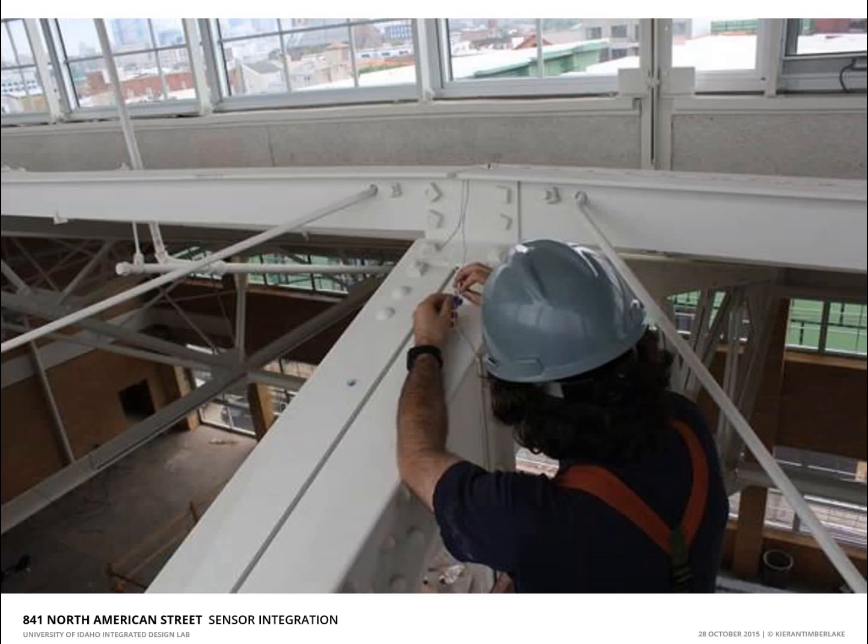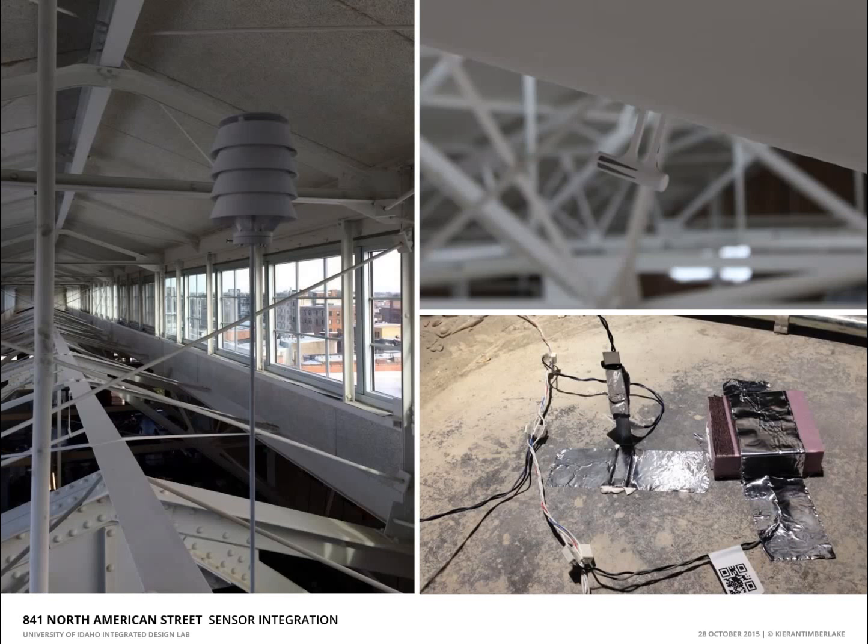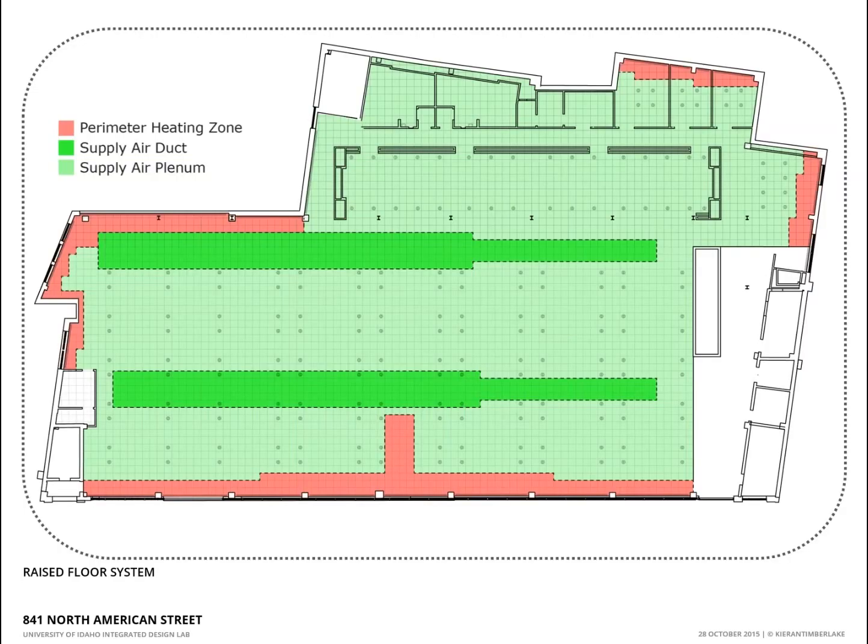So ultimately, we deployed a network that had a very strong performance and aesthetic agenda. So you can see on the left, we have some of these temperature readings taken from the large monitor that we have, where they're shielded from radiation, once again pulling from our own 3D printer to basically print a one-piece radiation shield. Then we also have our relative humidity sensors there on the upper right that we fabricated. And then we have the slab temperature, surface, core, and ambient temperatures in the underfloor system that were deployed as well. A little bit cruder, of course, because it's hidden. So all this equipment was used to basically understand how this particular system functioned.